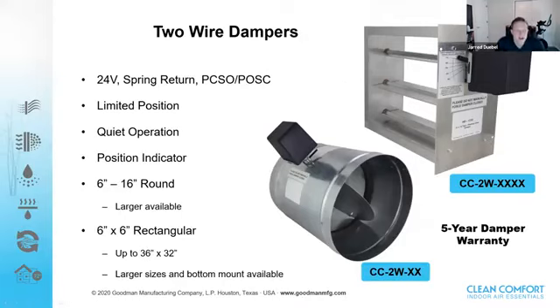Lastly, on these 2-wire dampers, so in a zoning type situation, your damper is typically going to be a power closed spring open. The reason we use a power closed spring open in zoning is because if we ever lost power to the panel, we want it to spring to the open position because we wouldn't want any zone being shut off. On the flip side of it, if you want to use one of our Clean Comfort dampers as a ventilation type damper, you can set it up in a power open spring close or power open spring return application, to where if it loses power, it comes back into the closed position, so you don't have an open hole from the outside of a home or living space that's going to allow air just to come in at any time. There is a position indicator on the damper.